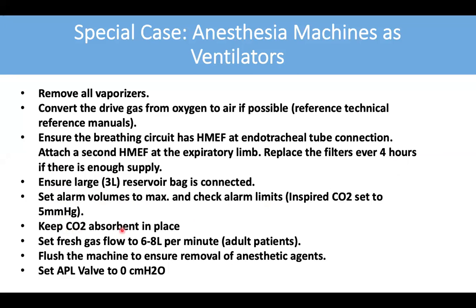You will keep the CO2 absorbent in place. You will set the fresh gas flow to minute ventilation, that is 6 to 8 liters per minute for adult patients. Make sure you flush the machine to remove all of the anesthetic agents from the system. You will set the APL valve to 0, and then you're able to change the mode from manual bag mode to vent mode, and you should be able to use your anesthesia machine as a ventilator.